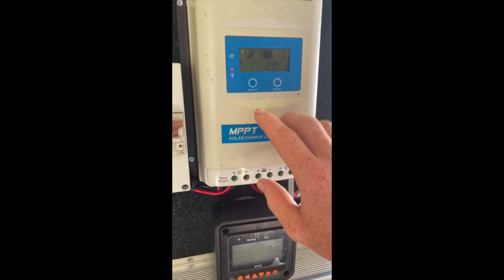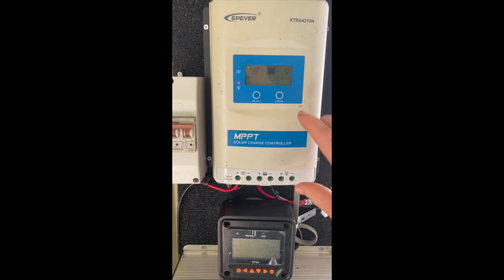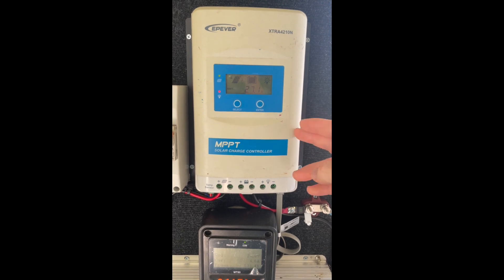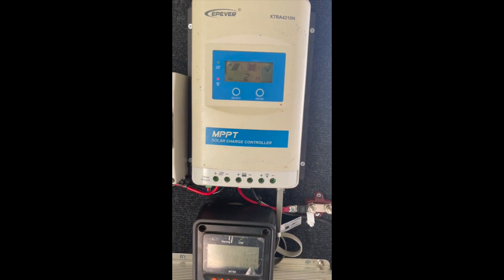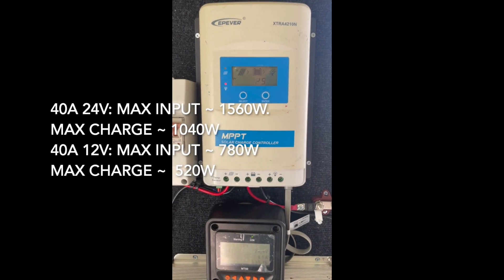From the circuit breaker it goes into the MPPT — this is the baby you want to know. This is a 40 amp, 12/24 volt unit. It's a 24 volt system I've got set up here. Essentially you can pull double the power or have double the size of the array going from 12 volt to 24 volt. We're only pulling 4.8 amps and that's giving us 130 watts of power. This thing can handle up to about a 1.5 kilowatt array — they can handle a lot of power.